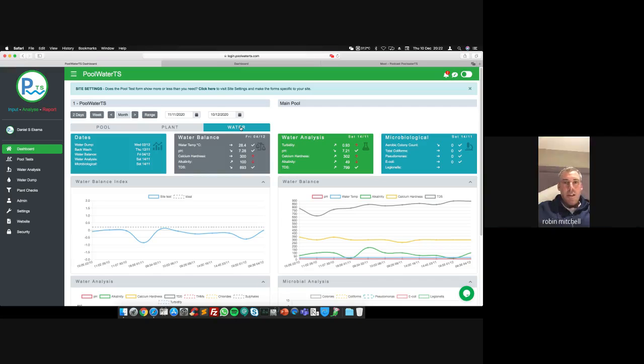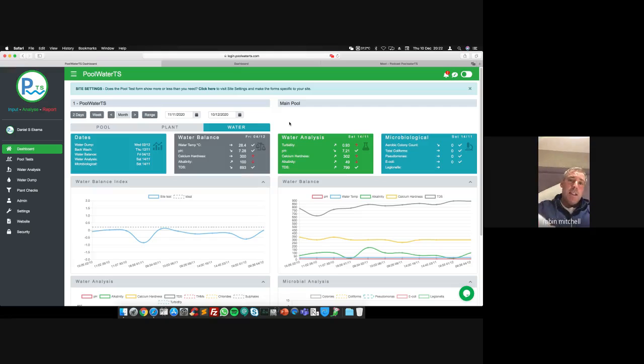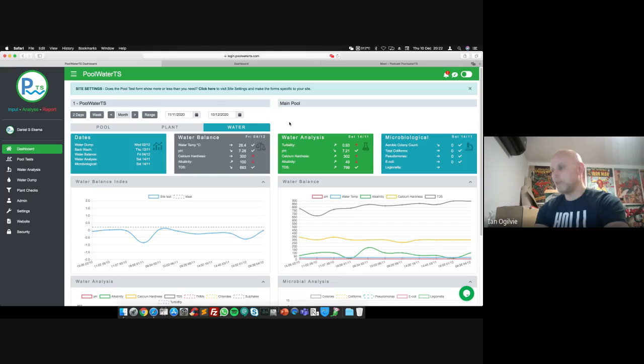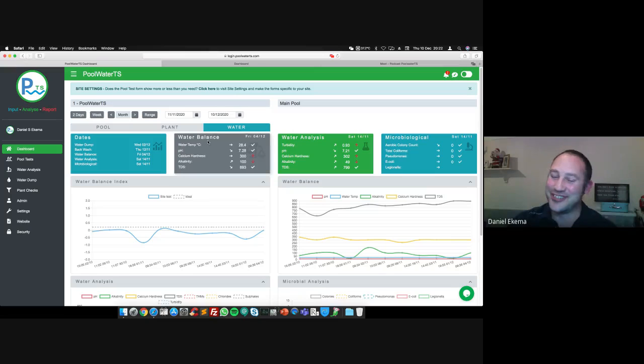Yeah, you're right. The TDS is very good, considering that you're using sulfuric and sodium hypochlorite, and that your calcium's up at 300. TDS. And you can see these are manually entered figures, though. I'm only kidding. Now, in fairness, we do have certificates to back up these water analysis ones. These are from a contractor.